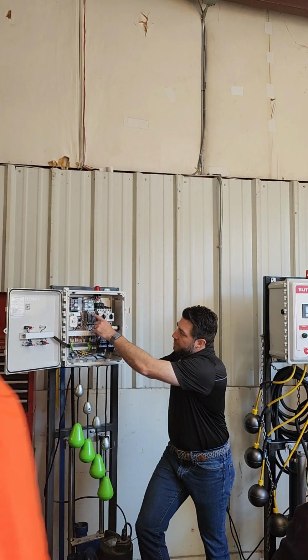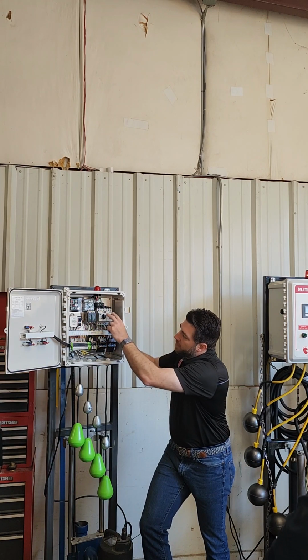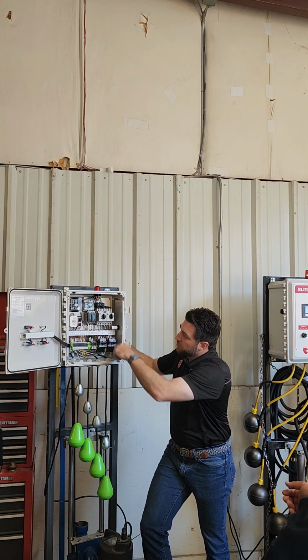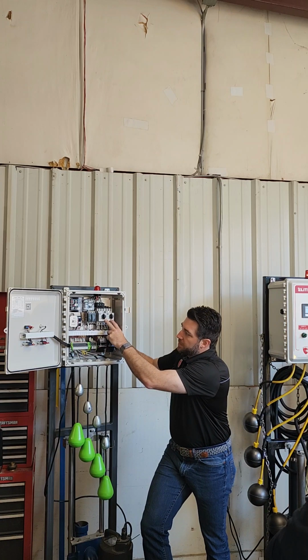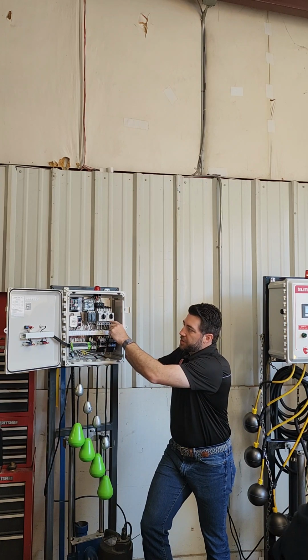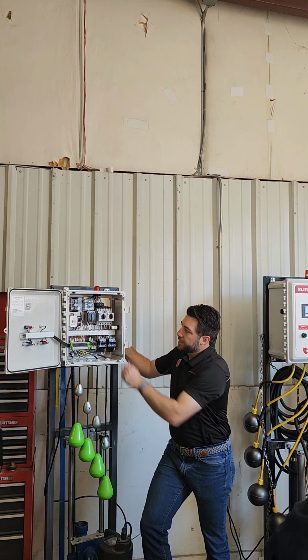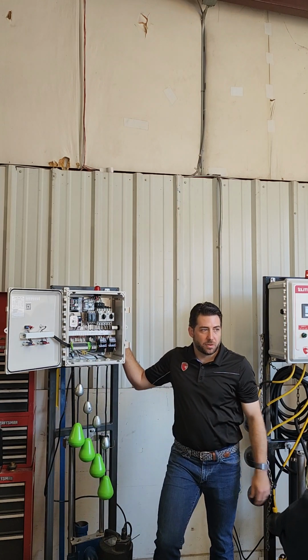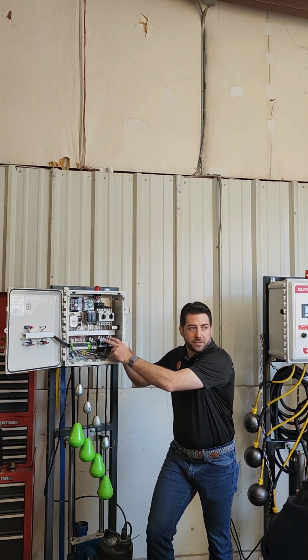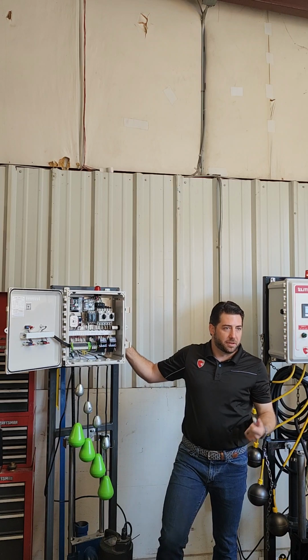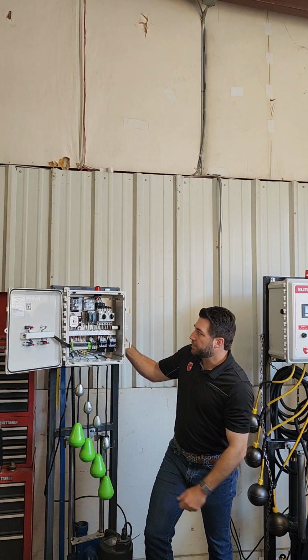Okay. So off of the disconnect, we're coming over here with a high voltage, and this is our motor control circuit. So we have a combination. This is a manual motor starter here. It acts as your circuit breaker or your disconnect there, as well as the overload. And then down here is the contactor. This is the relay that's pulling the motor in, the power in when we want to run the pump.